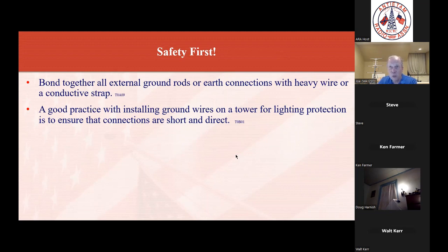This almost sounds like something out of a Roadrunner coyote cartoon. Think of that lightning going down the wire, screaming down really fast. Long and short, lightning doesn't like to make a turn. Having that bend in it will present challenges and will diminish the amount of lightning protection you're getting out of the system.